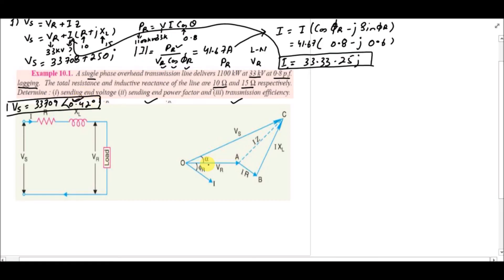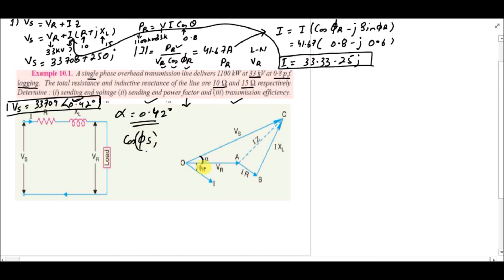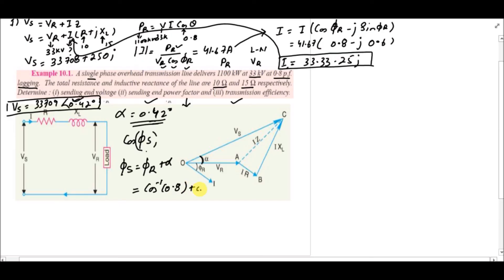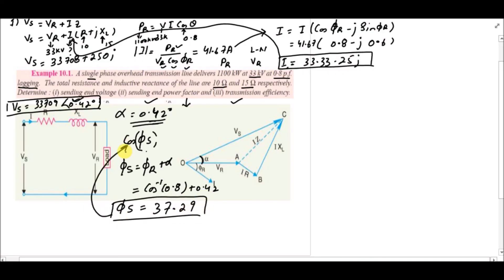The angle 0.42 degrees is with reference to VR, so alpha = 0.42 degrees. For the sending end power factor, phi_s = phi_r + alpha. Here phi_r = cos⁻¹(0.8) = 36.87 degrees, so phi_s = 36.87 + 0.42 = 37.29 degrees. The sending end power factor is cos(37.29°) = 0.7956 lagging.